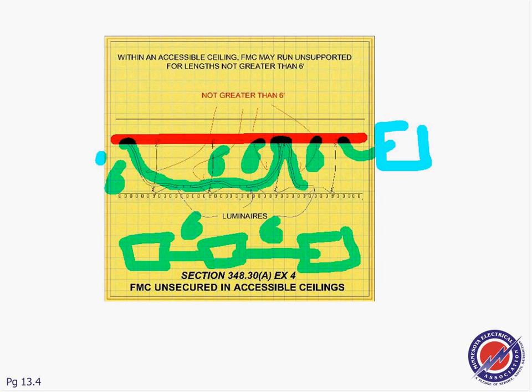So tying to a machine, like a transformer, like a panel, you can go all the way up to 5 feet. Remember, it's not a fixture whip. Fixture whip is 6. But for other than a fixture whip, other than equipment in a suspended ceiling, so that's not in a suspended ceiling, not a lighting fixture, then they allow you to go basically 3, 4, or 5 feet for flexibility based on the situation.